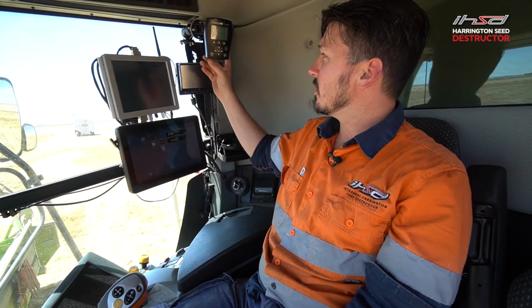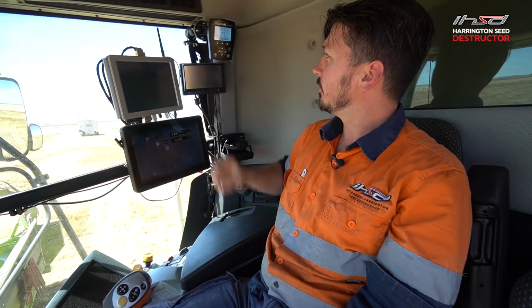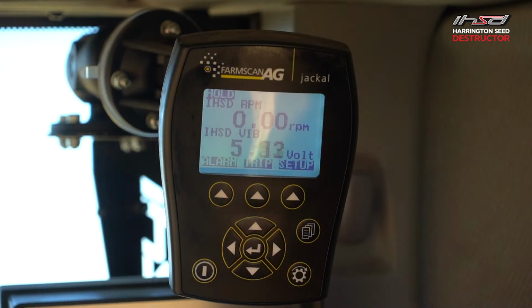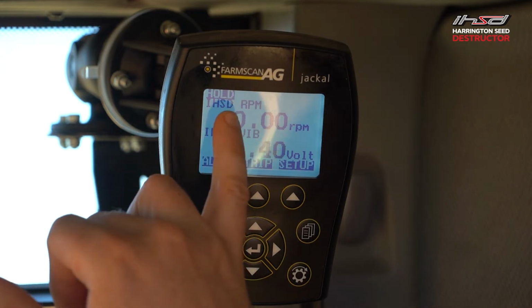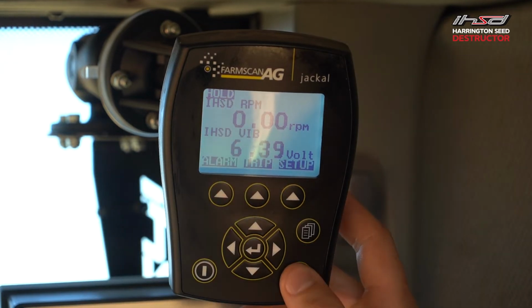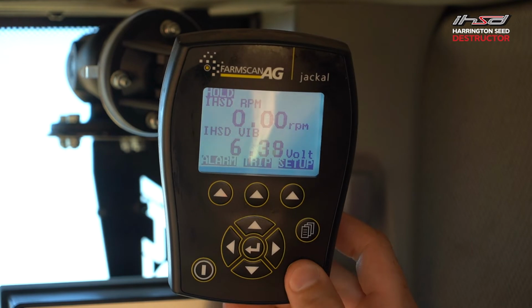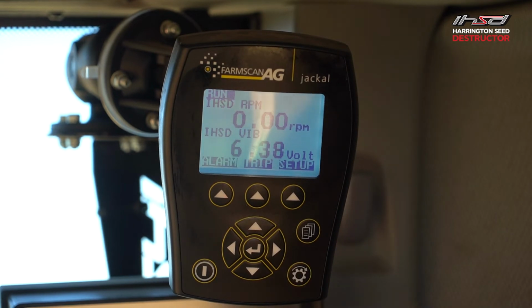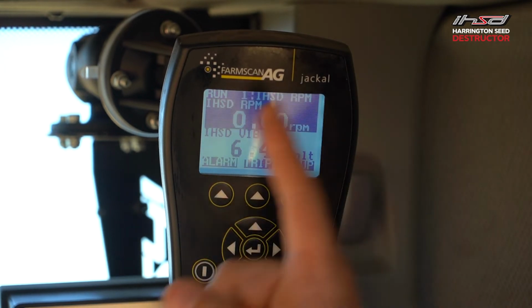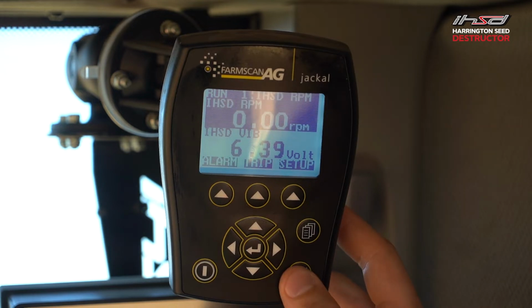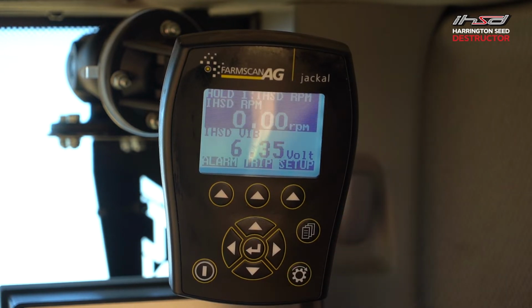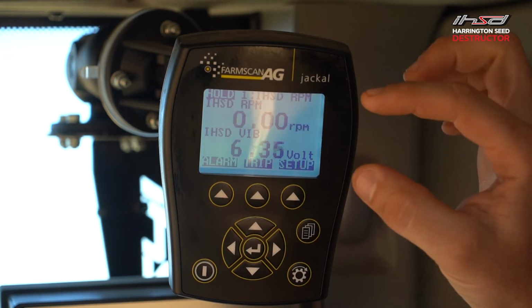Looking at the Jackal itself, we turn on and we start in hold mode. To change from hold mode to run mode, press the bottom right button. This will change to run. As you can see, an alarm comes on for the RPM. Changing back to hold mode, the alarm goes away. This is useful for when you need the Jackal on, but you don't want the alarms going. Moving on to the different types of readouts that we have.